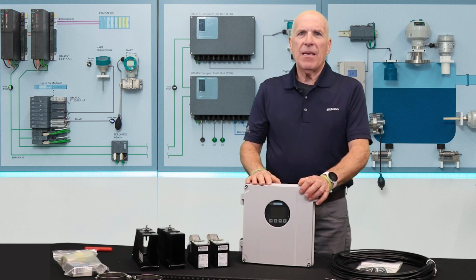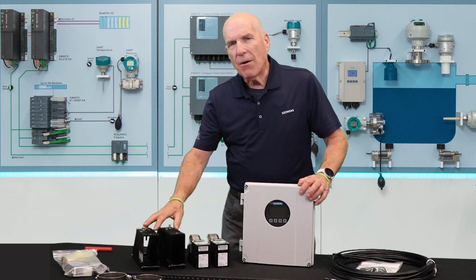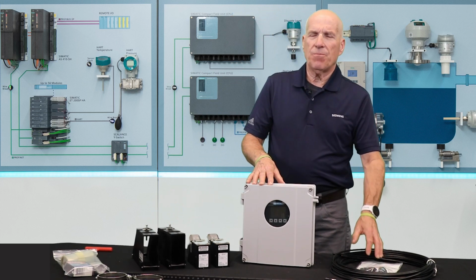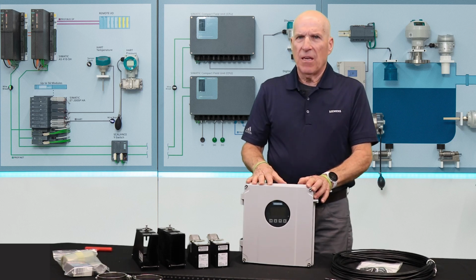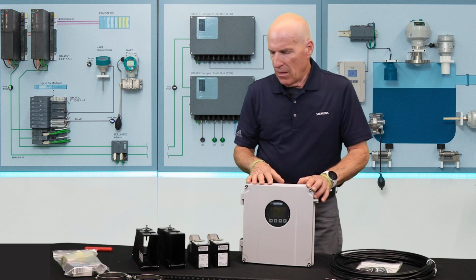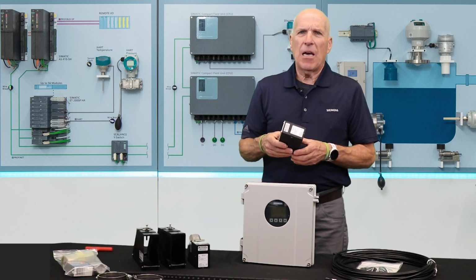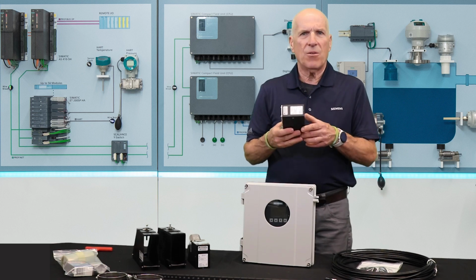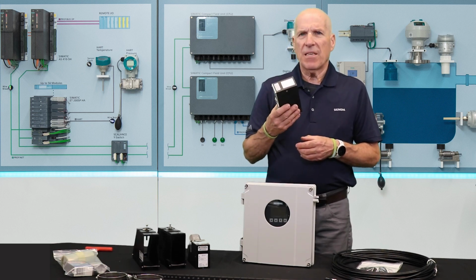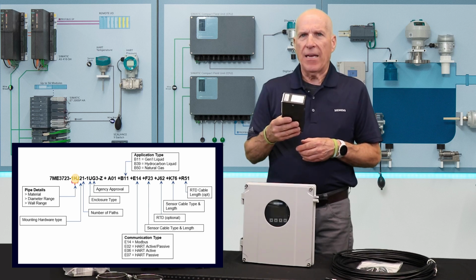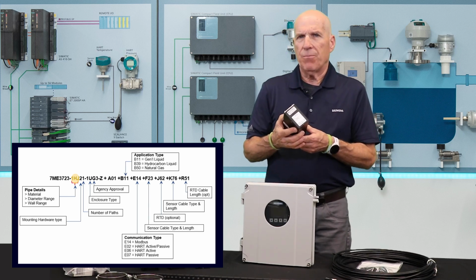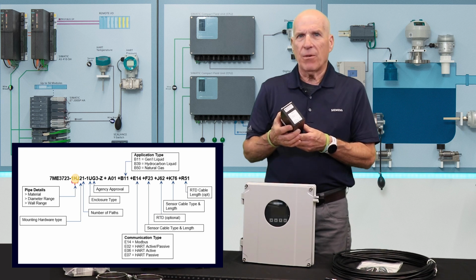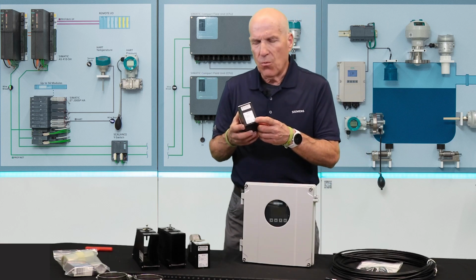Along with your transmitter, in the box you'll find your flow sensors, your mounting hardware, and your system cables. Since there are a number of options for each of these, let's take a closer look at what they are. Starting with the flow sensors, the type you receive will be determined by the code in your system part number. Seen here in this case, we have 1HJ. The 1 translates to a steel pipe, therefore high precision sensors are supplied. The HJ represents the diameter and wall thickness ranges, which determine the specific sensor size. Our sensors are size D1H high precision. They are identified as such on their own label.